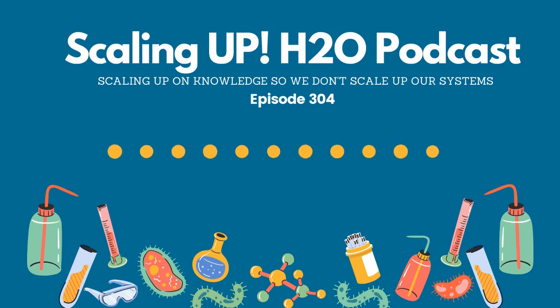It will also have the alloy number, and there are different types of alloys, as I mentioned. So this will have the specific alloy that's there, and then it will have the part number itself. And by the part number, like I said earlier, you're going to have a specific length, width and depth of the coupon. You're going to have a specific hole size. All of that is captured in that part number. So once you know which part number you need, you can simply keep ordering those over and over again from your favorite supplier.